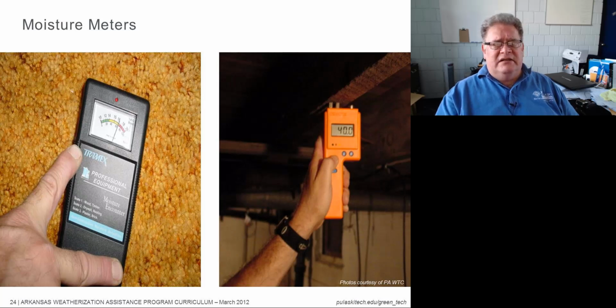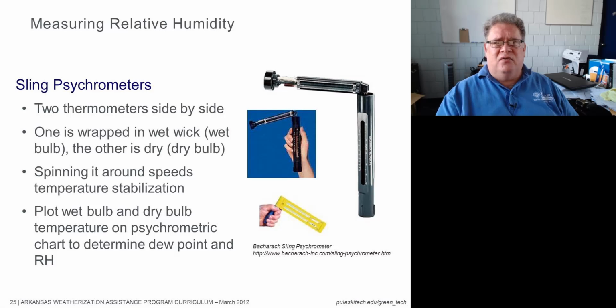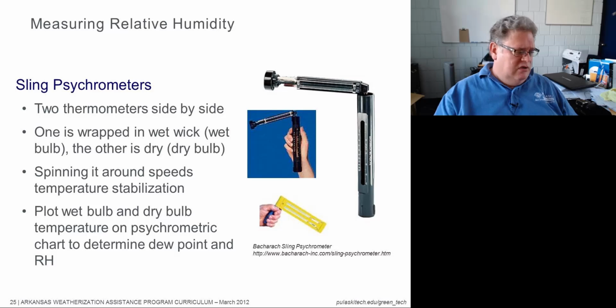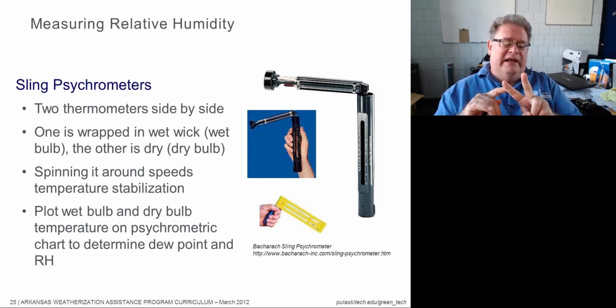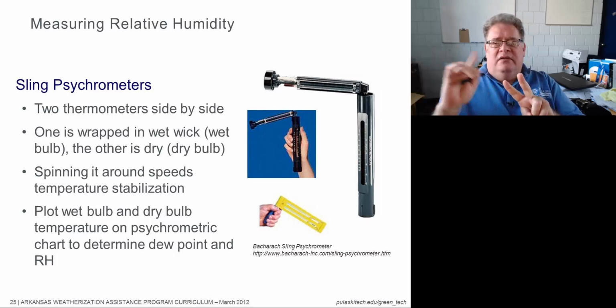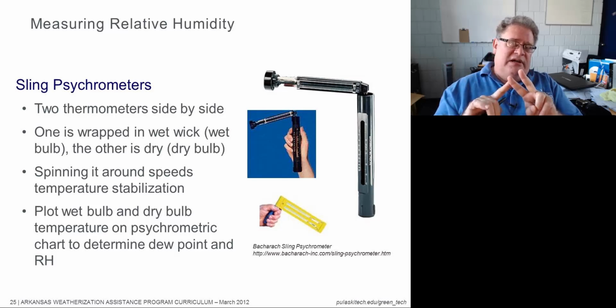Sling psychrometer, we were talking about measuring indoor relative humidity. Here, these things look really fancy, but you have a thermometer here and you have another thermometer here. You notice that the bulb on this one, that's what that brown spot is, is exposed. This bulb right here has some cotton batting up against it. The way these are used is you're actually testing 2 temperatures in the house. We put a few drops of water on the cotton batting, and then we rotate this at a certain speed. The energy that we put into it by rotating it is forcing evaporation off of the cotton batting. It's absorbing heat in order to evaporate from the thermometer, so as it absorbs that heat, it drops the temperature reading on the thermometer.